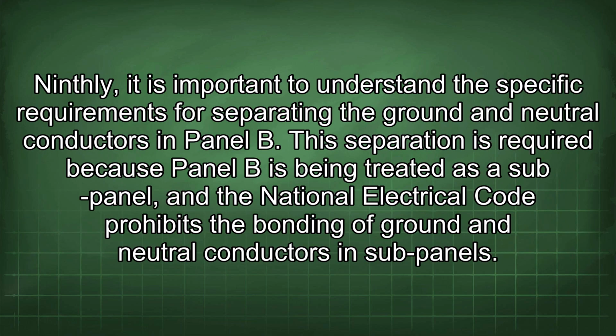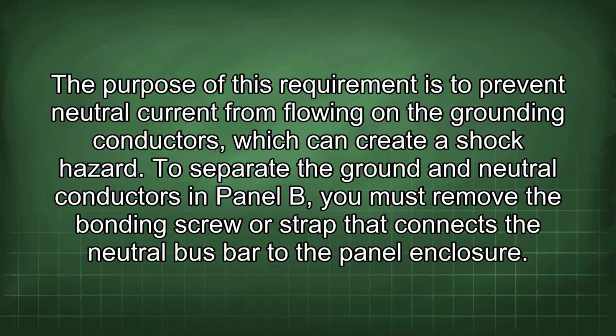Ninthly, it is important to understand the specific requirements for separating the ground and neutral conductors in panel B. This separation is required because panel B is being treated as a subpanel, and the National Electrical Code prohibits the bonding of ground and neutral conductors in subpanels. The purpose of this requirement is to prevent neutral current from flowing on the grounding conductors, which can create a shock hazard.